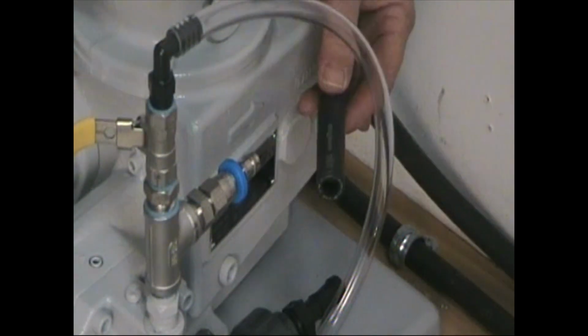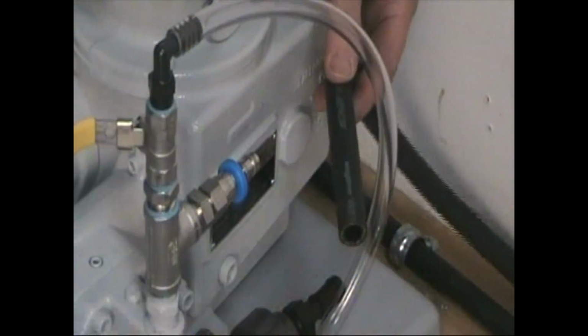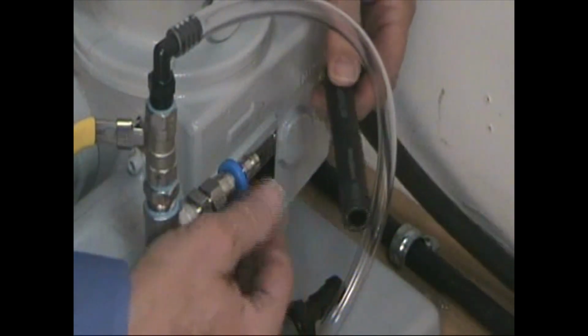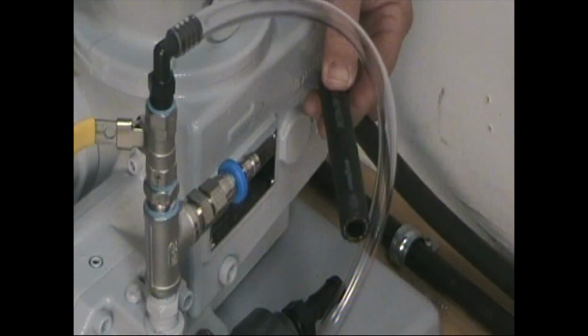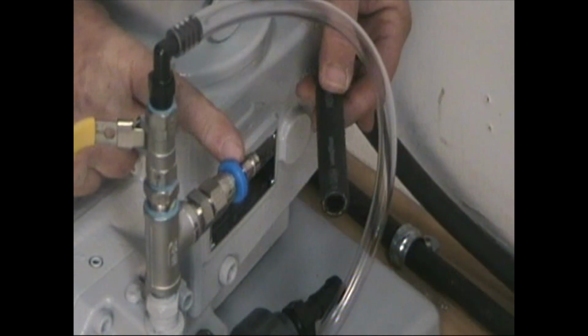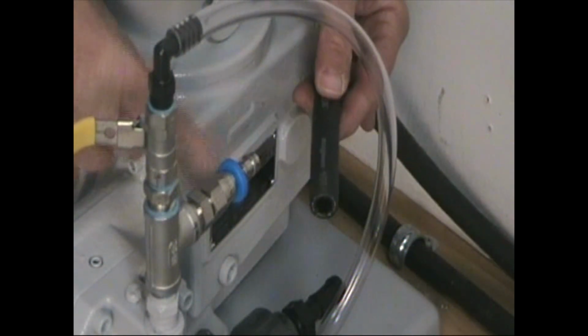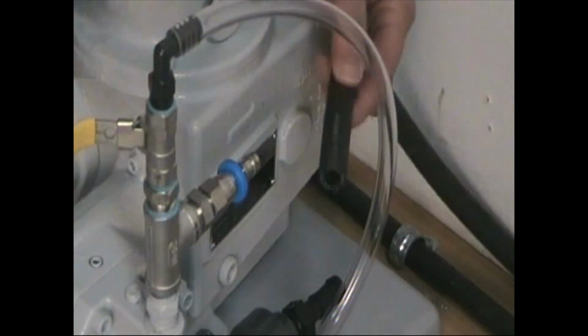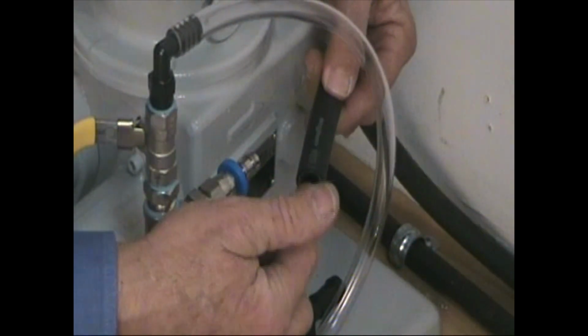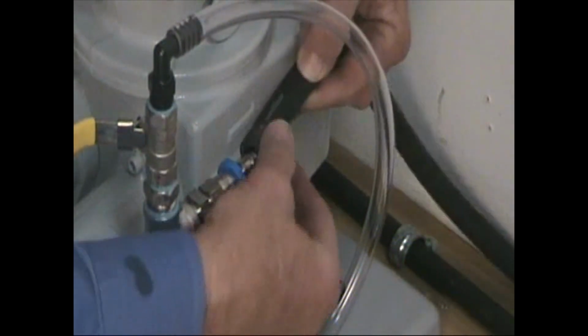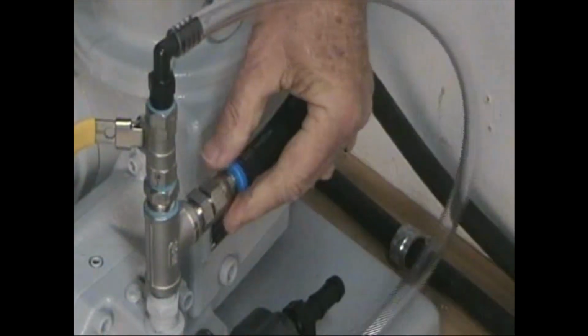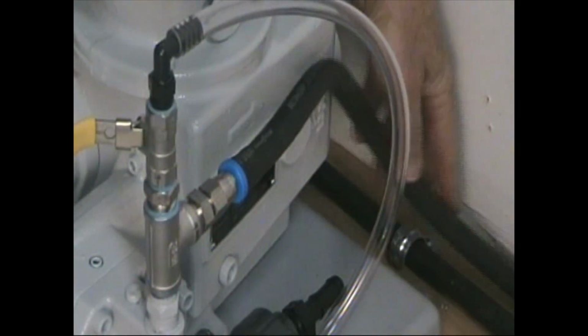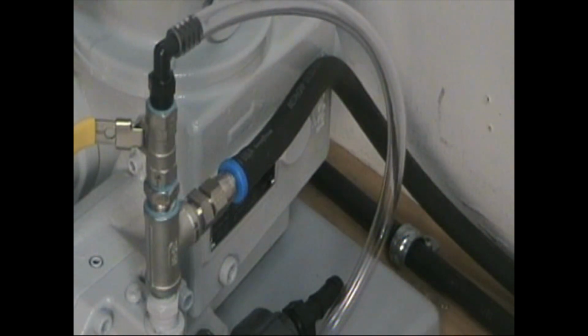Okay. Next thing you're going to do is install the discharge line. The discharge line is a special push lock hose, and it connects to the hose barb in a special way so that it will not need a clamp. You put thread sealer to lubricate the barb and the hose, and you push it on all the way until it hits the blue connector. And you do it for each side, and you'll be all set.